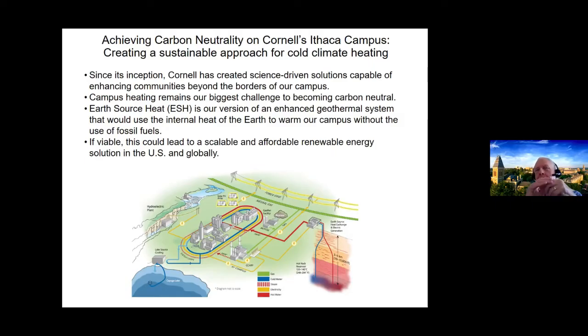The only problem with the Moscow-style system is its higher temperature—it was probably going in as steam, which results in a lot of losses. You see some of those losses when you see snow melting. The idea of a real modern heating system now is to go to very low temperatures. We have hundreds of kilometers of distribution piping underground at the campus, and the losses go down because the temperatures are lower, so you have less heat loss. That's a big plus.